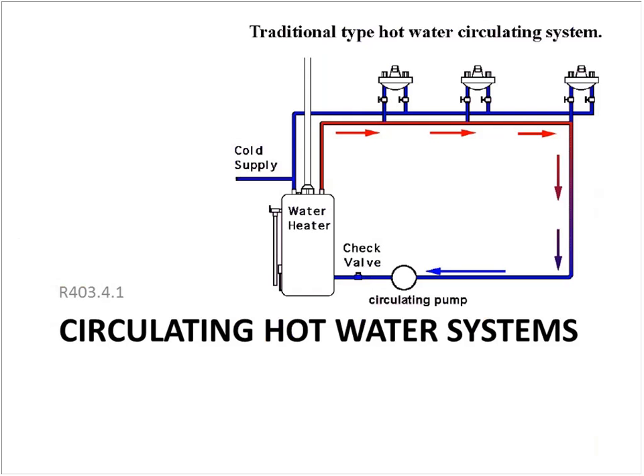Circulating hot water heating systems are required to be insulated, and that's covered under R403.4.1. This is the traditional hot water recirculating system. We don't see a lot of those anymore. Occasionally we still find them, so those are the requirements. All recirculating service hot water piping shall be insulated to at least R-2. Circulating hot water systems shall include an automatic or readily accessible manual switch that can turn off the hot water circulating pump when the system is not in use.